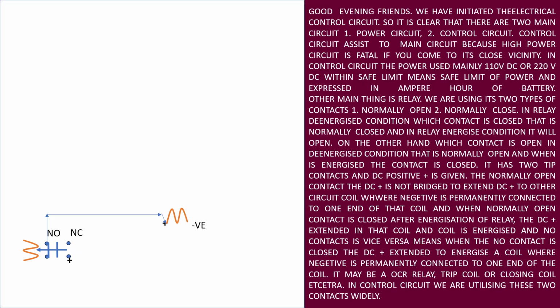And in the traction substation, I have already told, when DC supply fails, it is very dangerous because the relay will not work. So the circuit breaker will not trip, because the circuit breaker trips through the DC tripping coil and closing coil. If DC fails, it will not trip, and if there is any fault in the OHE, there will be a fire accident.